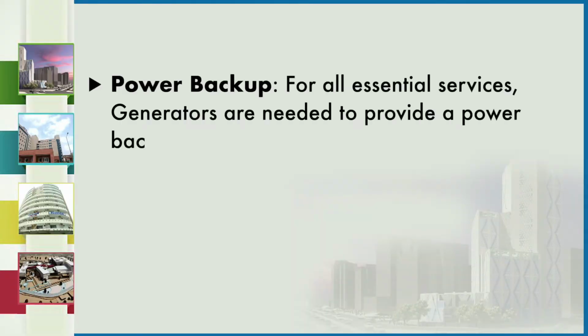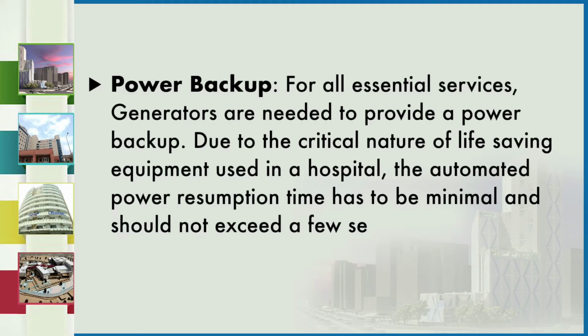Power backup for all essential services has to be provided. Generators are needed to provide a power backup. Due to the critical nature of life-saving equipment used in a hospital, the automated power resumption time has to be minimal and should not exceed a few seconds.